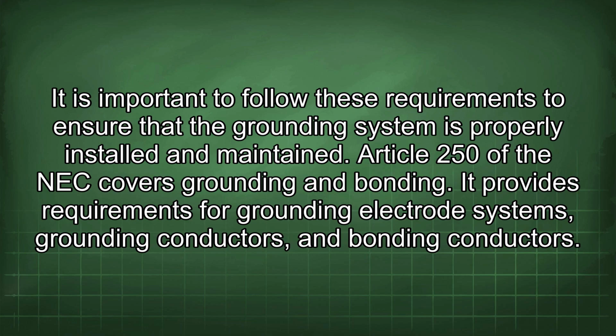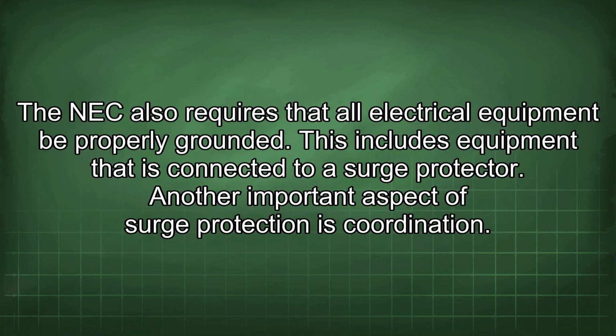It provides requirements for grounding electrode systems, grounding conductors, and bonding conductors. The NEC also requires that all electrical equipment be properly grounded. This includes equipment that is connected to a surge protector. Another important aspect of surge protection is coordination.